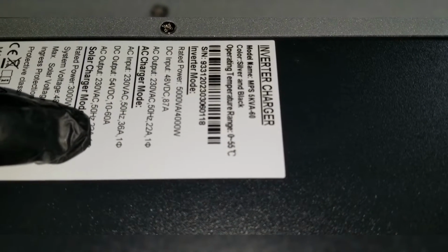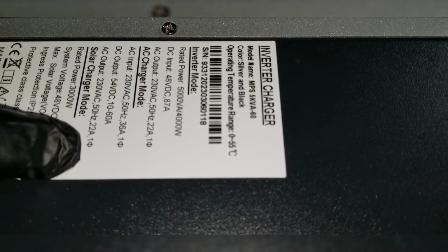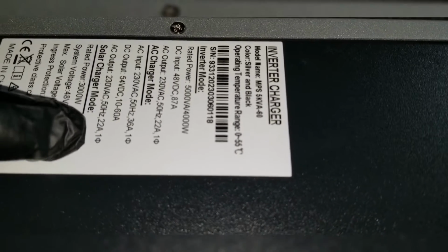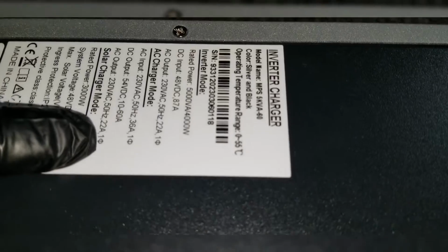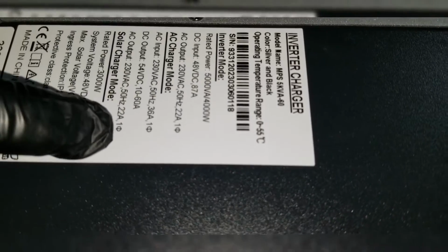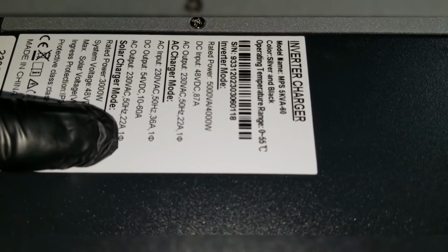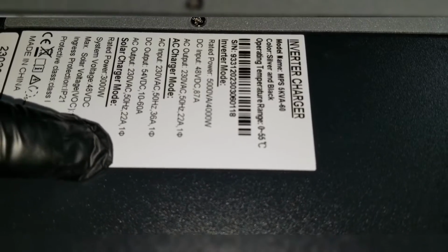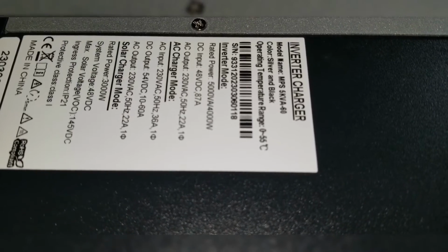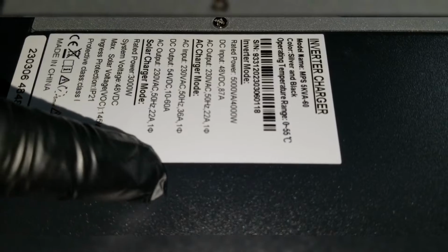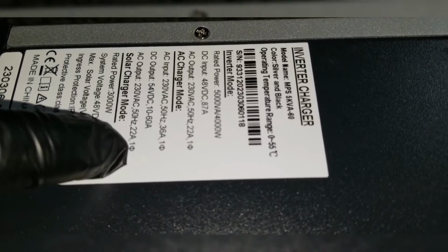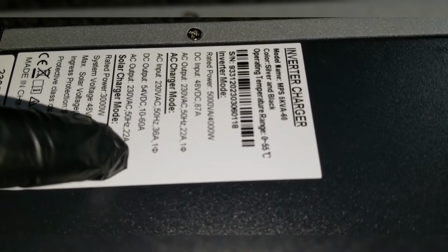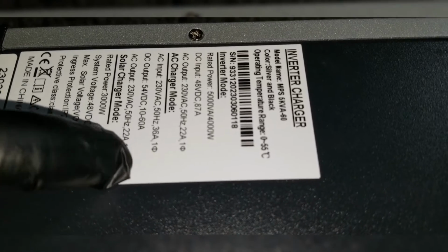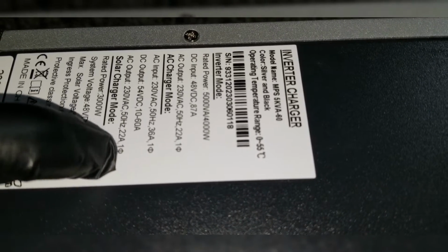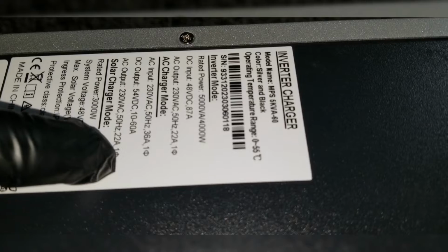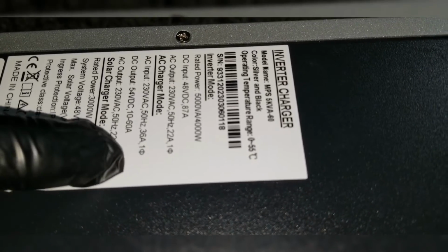So 22 amps is what it's putting out on the AC side. You need approximately a 25 or 30 amp breaker going to your disconnect or sub panel. You can go with 25 amp, or if you don't have that, use a 30 amp breaker. Don't try to use a 20 amp — it's not going to work, or rather it will work, but it will trip.